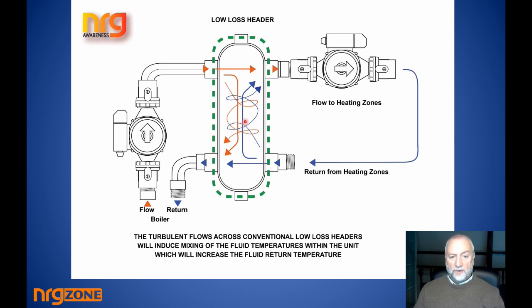To my mind, putting in low loss headers and systems that do not allow for the maximum effect from separating the hottest from the coldest is contradictory to the fact that you want the most efficient system. Likewise, when zones are taking away heat, if they're getting some of the return water, they're not going to be delivering as much energy. If they're not delivering as much energy, then clearly they're not being as efficient as they could be. And in that scenario, the zone efficiencies drop, the boiler efficiency has to drop if you've prevented condensation, or the proper COP of a heat pump. So therefore it can't be a good idea.